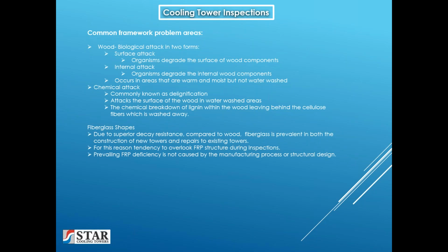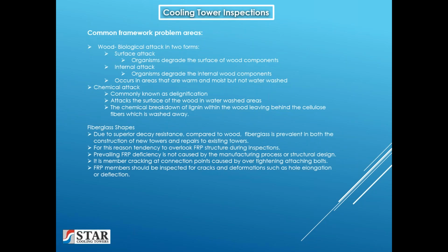The prevailing FRP deficiency is not caused by the manufacturing process of the fiberglass or the structural design of the structural members by the OEM. It is member cracking at connection points caused by over-tightening attaching bolts. FRP members should be inspected for cracks and deformations such as hole elongation or deflection. UV damage can range from fading and chalking to more advanced instances of fiber blooming, which is exposed glass fibers.